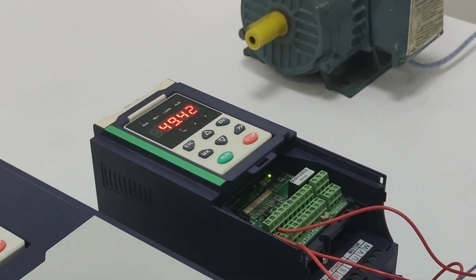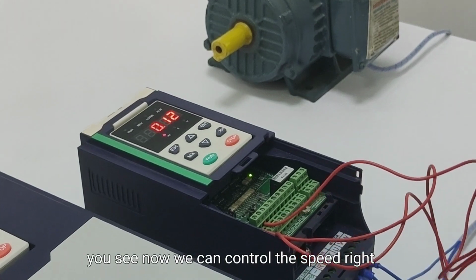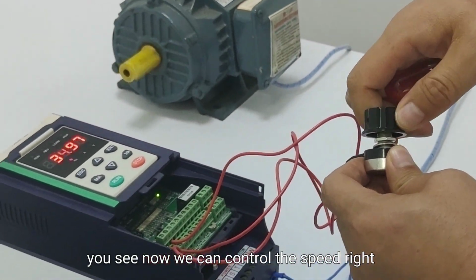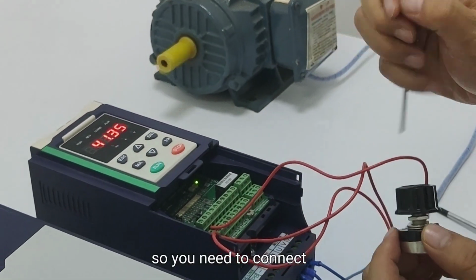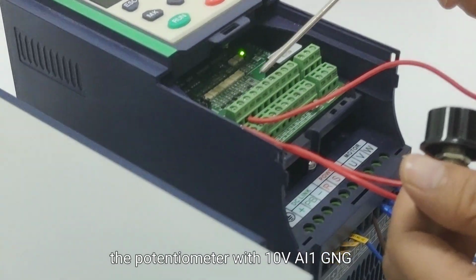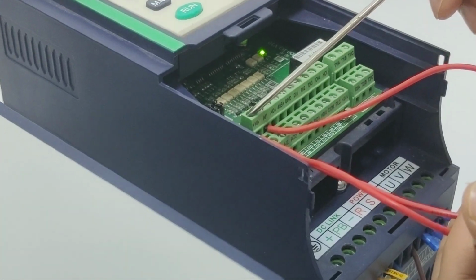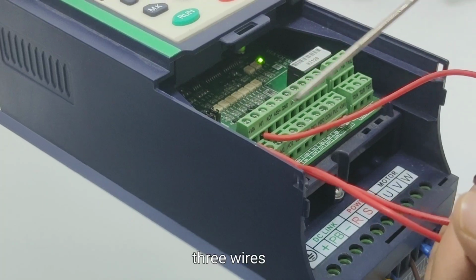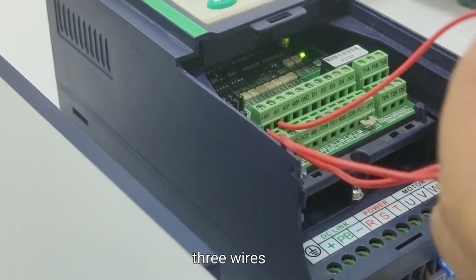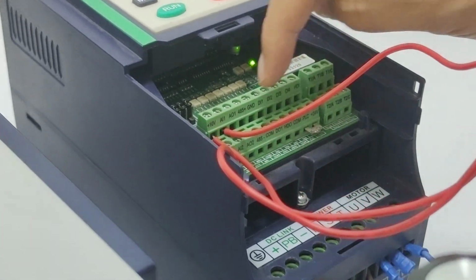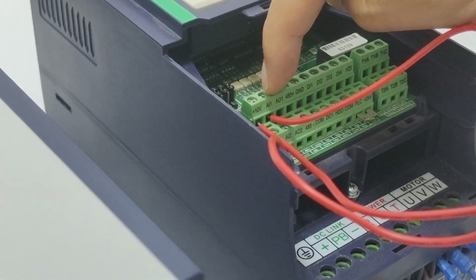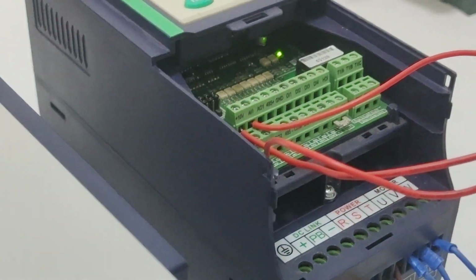Okay? You see, now we can control the speed, right? So you need to connect the potentiometer with the 10 voltage, AI1 and GND, 3 wires. 1, 2, 3, 3 wires, 10 voltage, AI1 and GND.